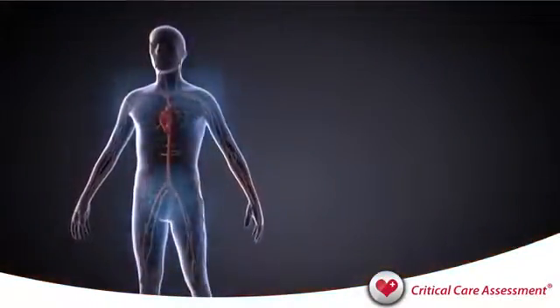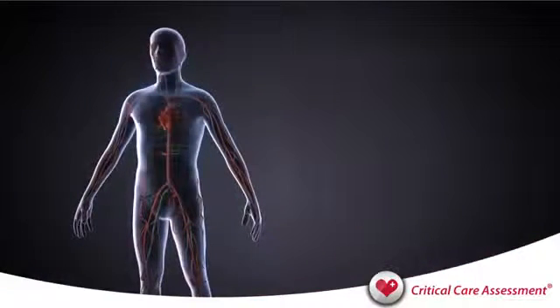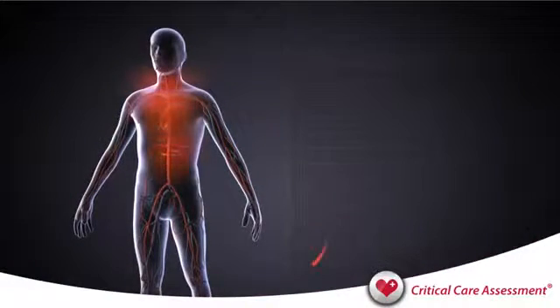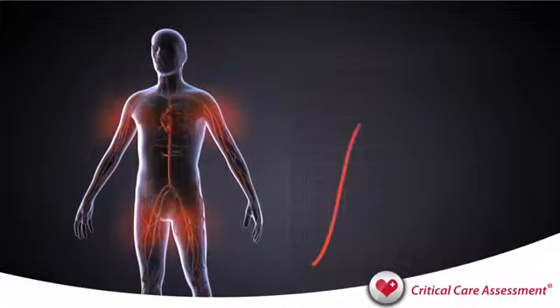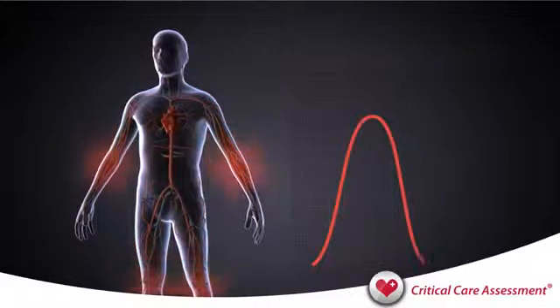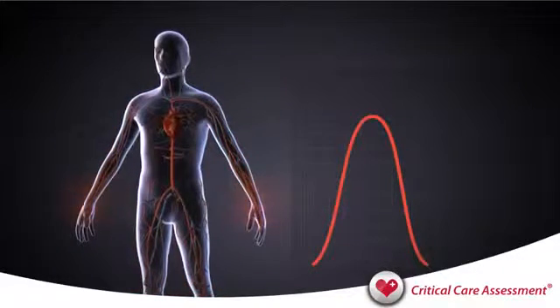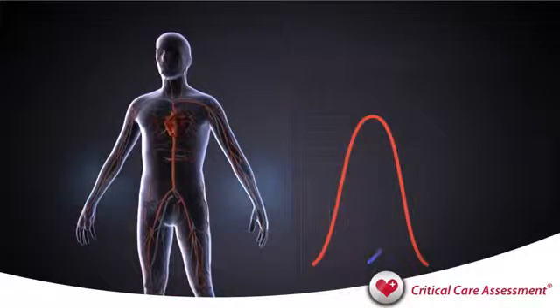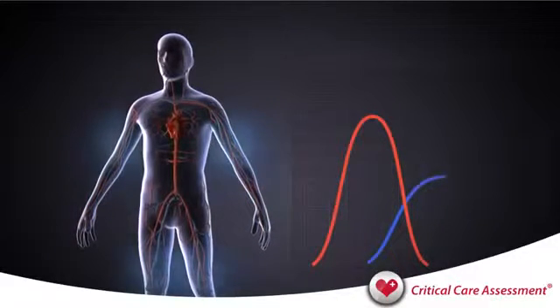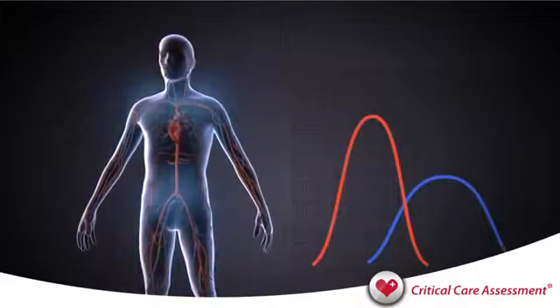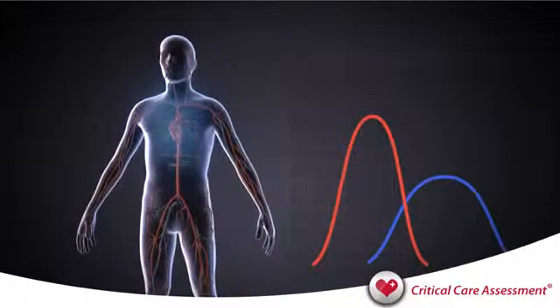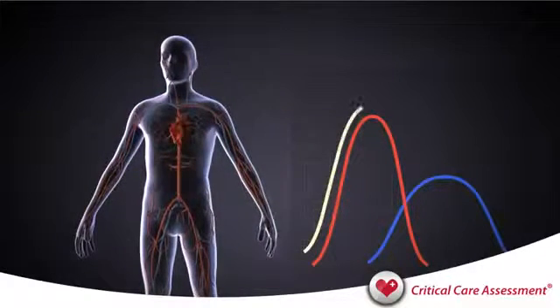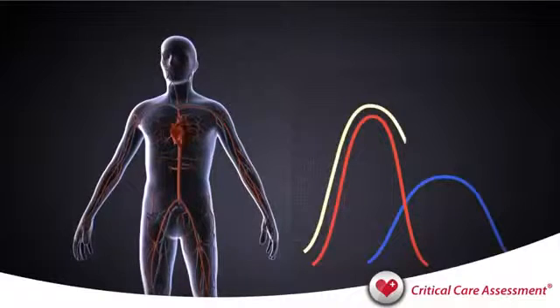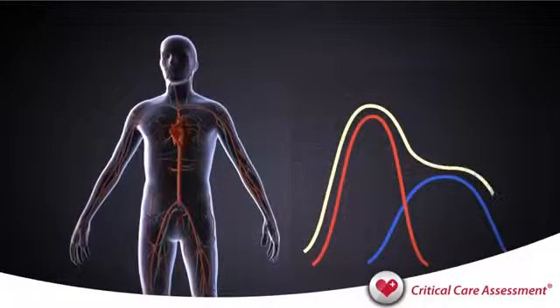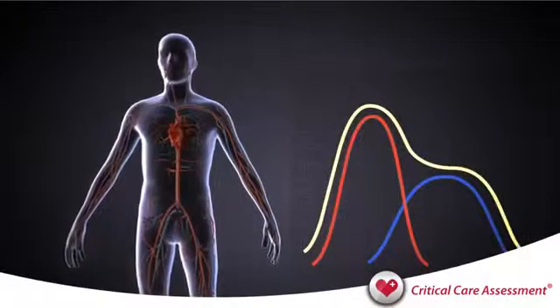Pulse wave velocity is measured by the finger probe. As the heart contracts, it creates a direct wave which travels down the arm, represented by the red curve. The direct wave is reflected in the lower body and travels backward toward the arm, represented by the blue curve. The direct wave and the reflected wave combine to form the dicrotic notch, represented by the yellow curve. Pulse wave velocity is an indicator of cardiovascular health, disease progression, and treatment status.